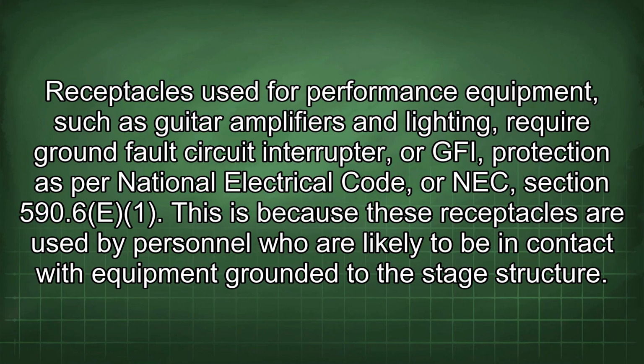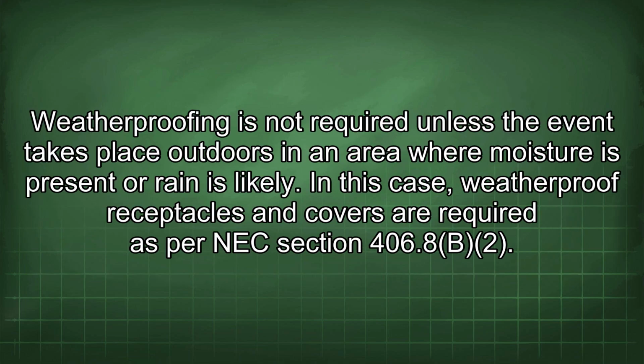Receptacles used for performance equipment, such as guitar amplifiers and lighting, require ground fault circuit interrupter, or GFI, protection as per National Electrical Code, or NEC, section 590.6(E)(1). This is because these receptacles are used by personnel who are likely to be in contact with equipment grounded to the stage structure. Weatherproofing is not required unless the event takes place outdoors in an area where moisture is present or rain is likely.